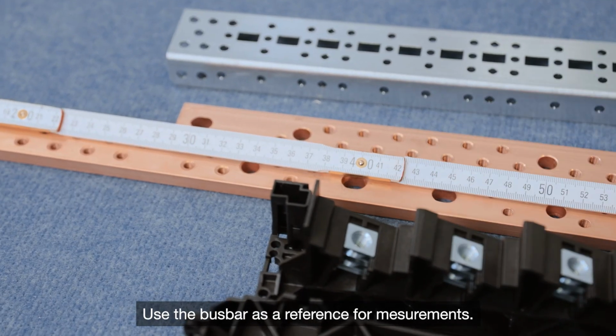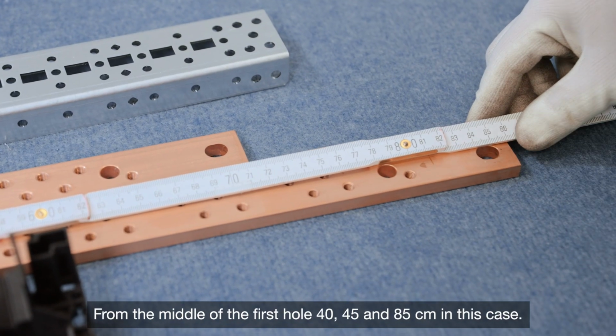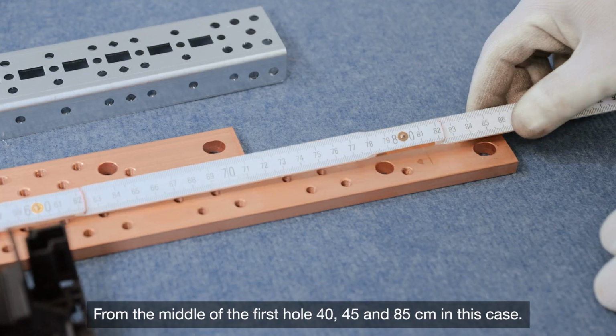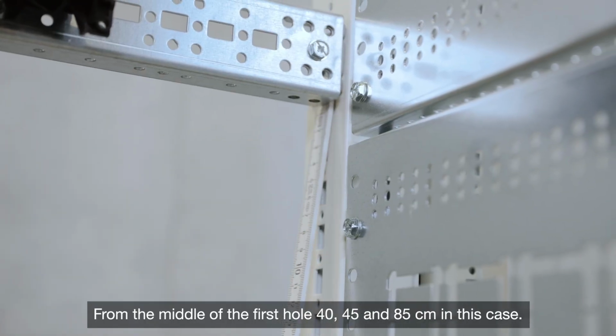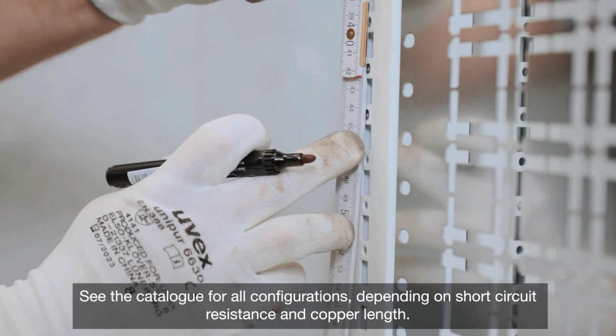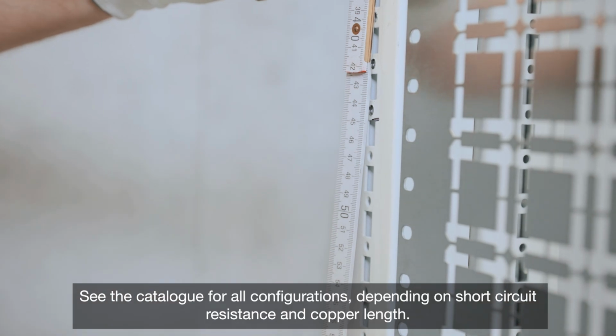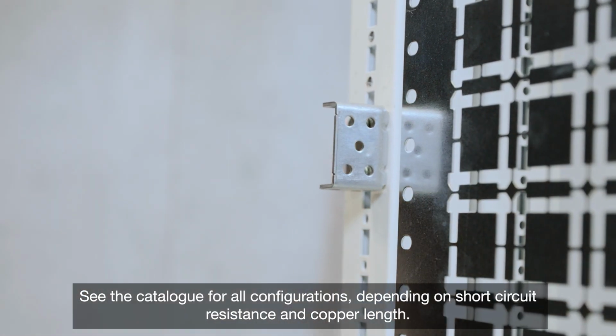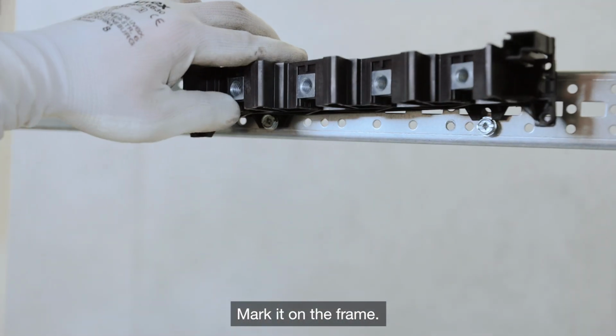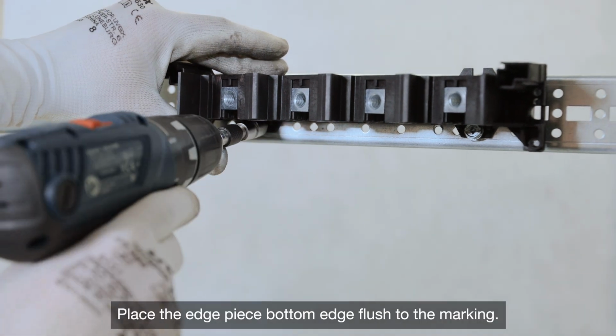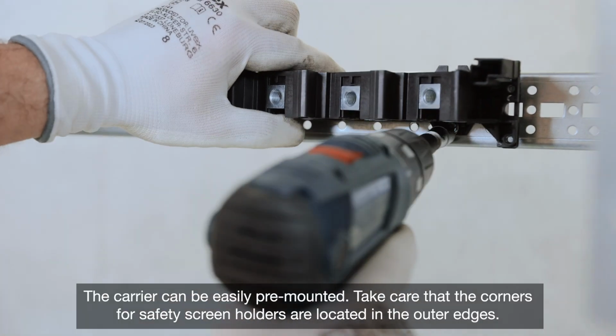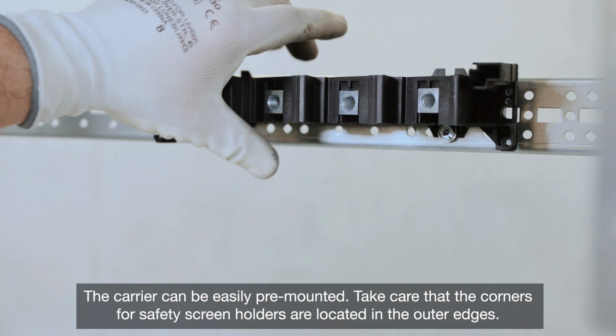Use the busbar as a reference for measurements. From the middle of the first hole: 40, 45, and 85 centimeters in this case. See the catalog for all configurations, depending on short circuit resistance and copper length. Mark it on the frame. Place the edge piece bottom edge flush to the marking. The carrier can be easily pre-mounted.